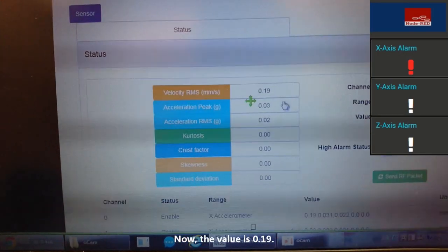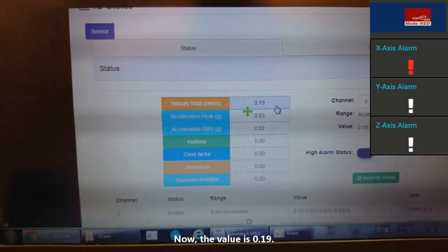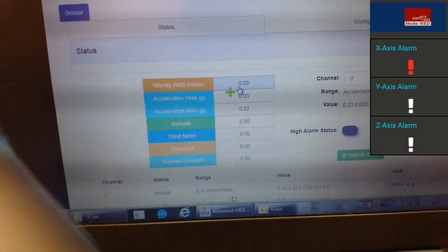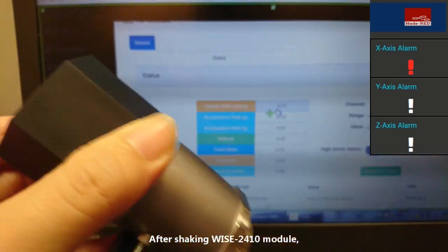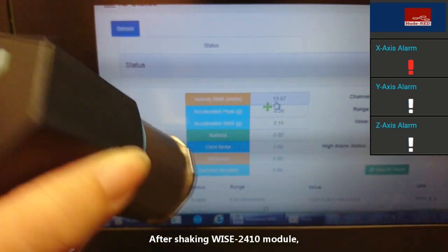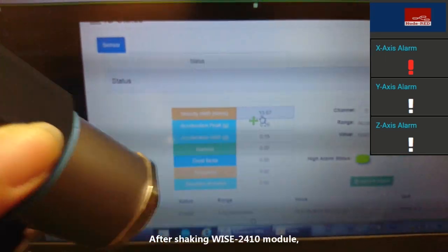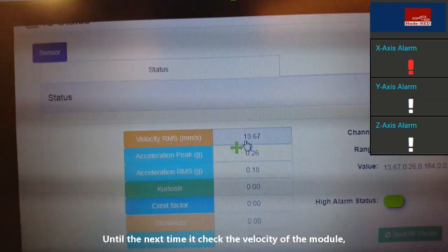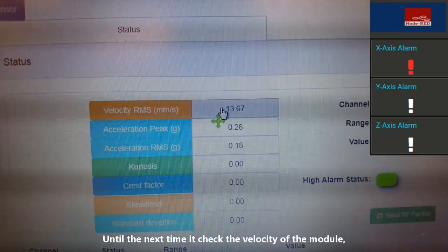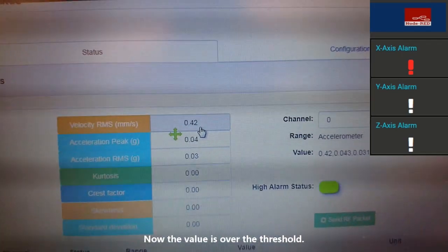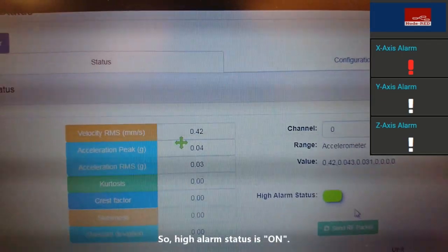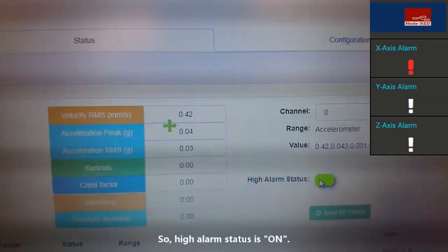Now the value is 0.19. Now I shake WISE module. Until the next time, it checks the velocity of the module. Now it's over 0.4. So high alarm status is on.